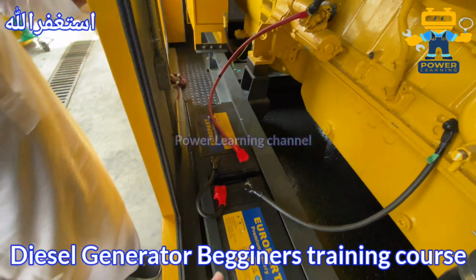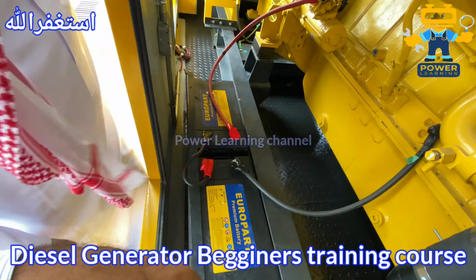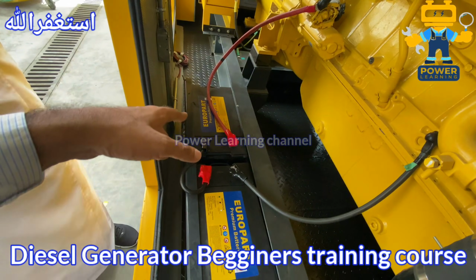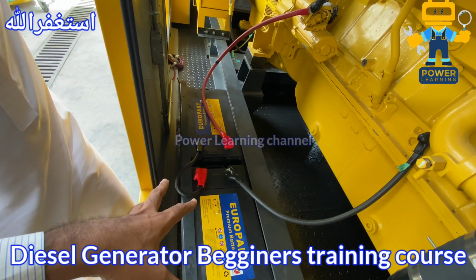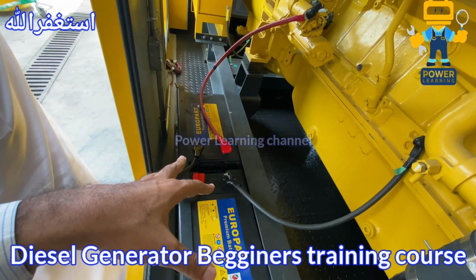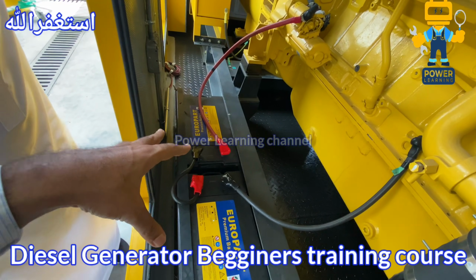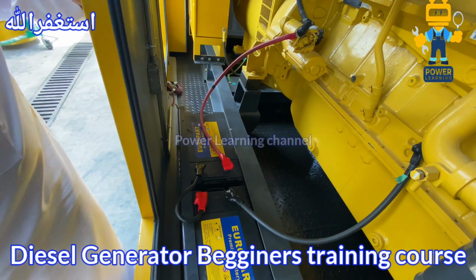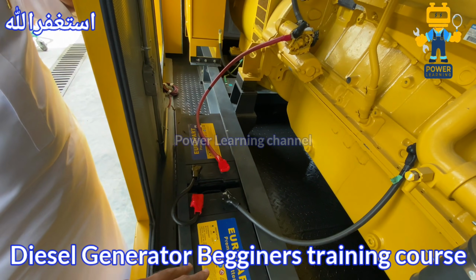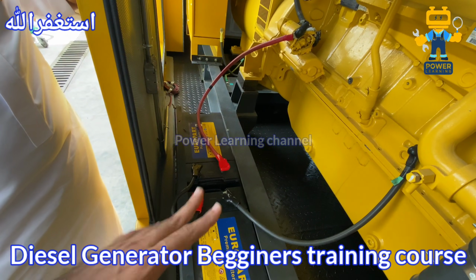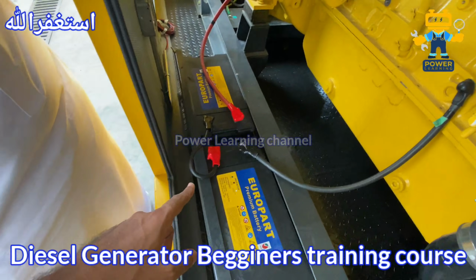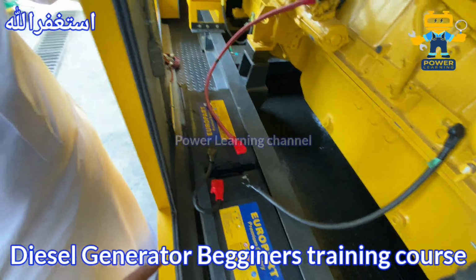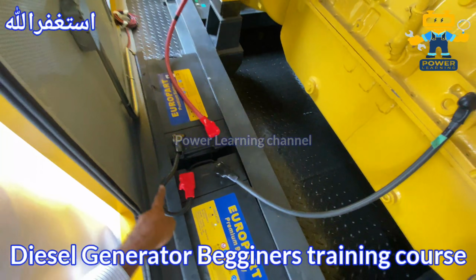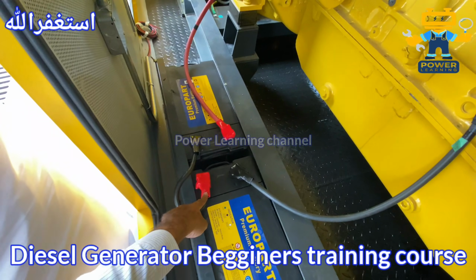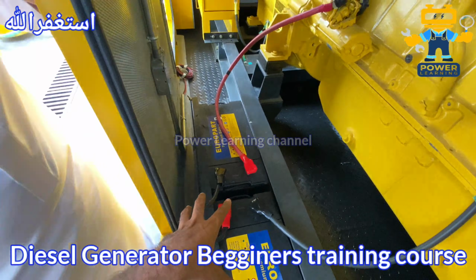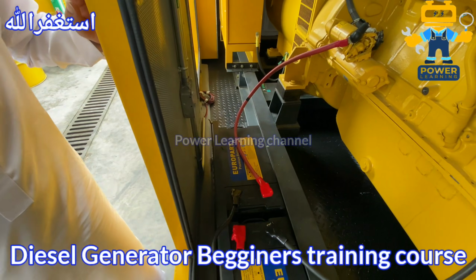Now the third thing is our batteries. These two batteries we are using as per the recommendation of the manufacturer, that this size should be suitable for this generator. This is a 500 kVA generator, so we put here 2 batteries of 200 amp-hours. These 2 batteries are connected in series. As you see, this is the series jumper. We connect the negative and positive together, so two 12-volt batteries will generate 24 volts together.